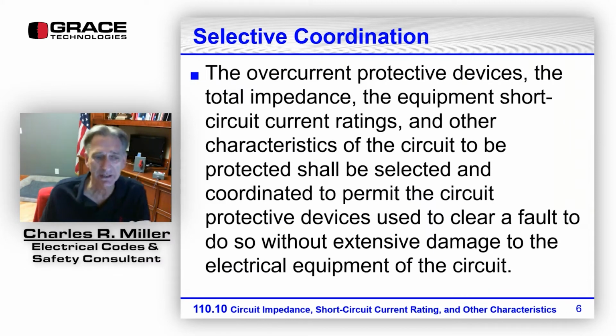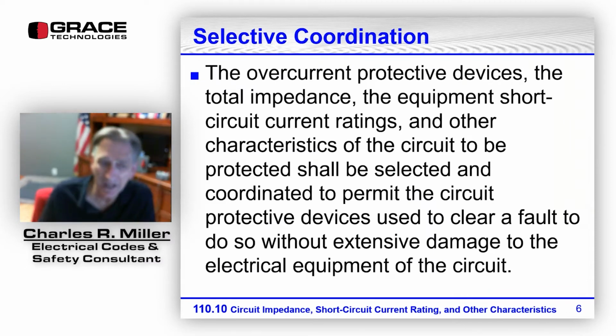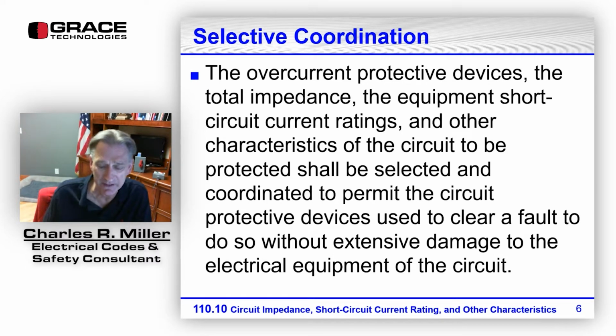Selective coordination, 110.10. This is not titled selective coordination. The title of this section in 110.10 says circuit impedance, short-circuit current ratings, and other characteristics. The section says the overcurrent protective device, the total impedance, the equipment short-circuit rating, and other characteristics of the circuit to be protected have to be selected and coordinated to permit the circuit protective device used to clear a fault to do so without extensive damage to the electrical equipment of the circuit. This is typically referred to as selective coordination.